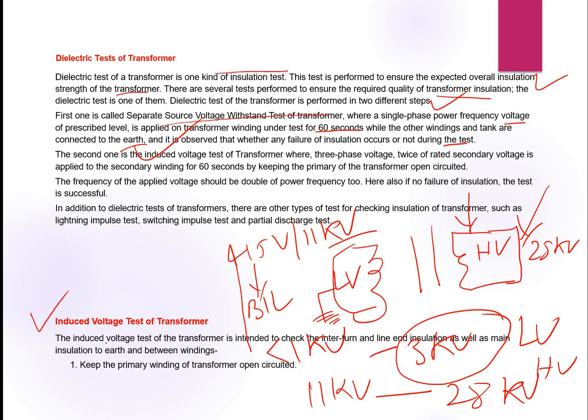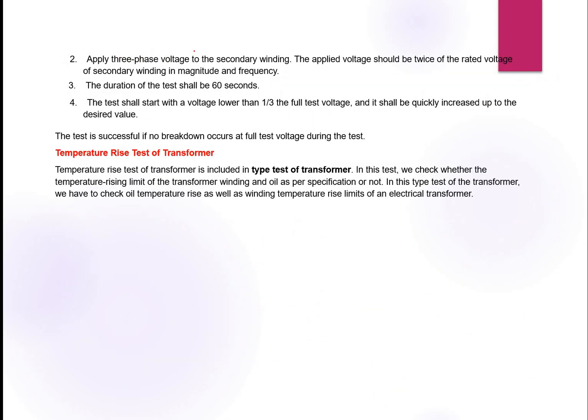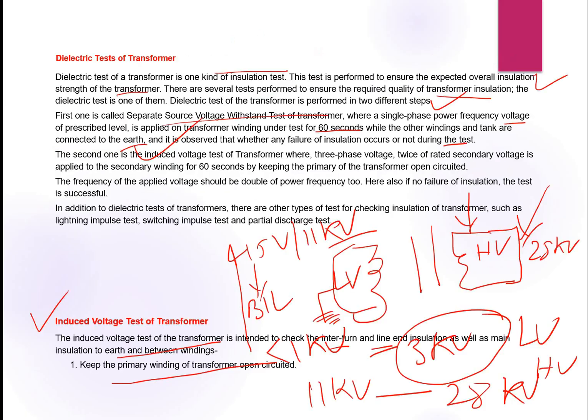And induced voltage test on transformer. The induced voltage test of transformer is intended to check the inter-turn and line end insulation as well as main insulation to earth and between the windings. Keep the primary winding of the transformer open circuited, and apply the three phase voltage to the secondary winding. Applied voltage should be twice the rated voltage of the secondary winding in magnitude and frequency, and duration of the test is 60 seconds. The test shall start at a voltage lower than one third of the full test voltage and shall be quickly increased up to the desired voltage. Okay, this is the induced voltage test.